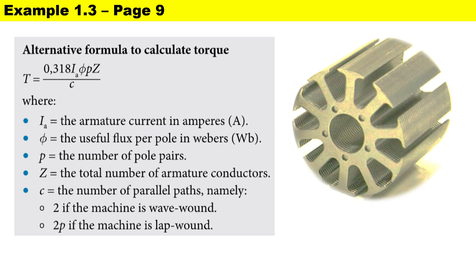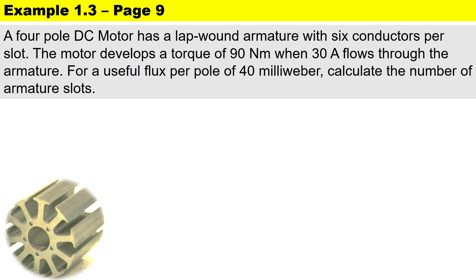For lap wound, the number of parallel paths is the same as the number of poles. In this example, a four-pole DC motor has a lap wound armature with six conductors per slot. The motor develops a torque of 90 newton meters when 30 amperes flows through the armature, for a useful flux per pole of 40 milliweber. Calculate the number of armature slots.